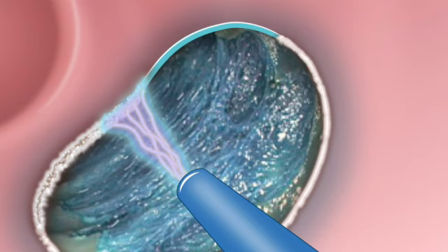But the term you mentioned earlier, monopolar circuit, is critical here. Right, because the energy has to go somewhere. Exactly. Once that electrical current crosses the glowing plasma bridge and hits the mucosa, the energy doesn't just vanish. The human body actually has to become the return path for the circuit. Which means the patient has to be physically hooked up to the generator in another way to complete the loop. They do. The patient is connected to a returning electrode, which is typically just a neutral electrode pad placed on their skin, like on their thigh. Okay, I've seen those. Yeah, so the high-frequency current flows from the generator, down the endoscope, across the plasma beam, into the target lesion, safely through the patient's body tissues to that neutral pad, and then right back to the generator. It's a continuous closed loop of energy.